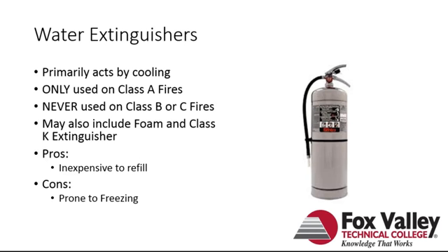If you put water onto a Class B fire, all you're going to do is spread the fuel. I'm sure we've heard the stories about a small grease fire. You hit it with water, and all of a sudden now you just put your fuel all over the rest of the room. And Class C, for obvious reasons. Energized electrical equipment, you're dealing with water, it's going to come back and it's going to shock you.